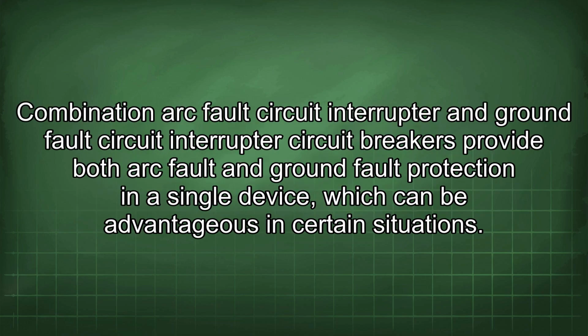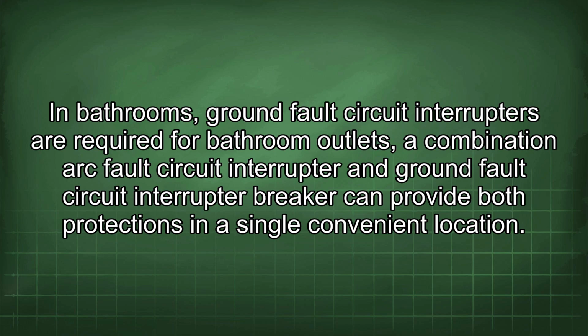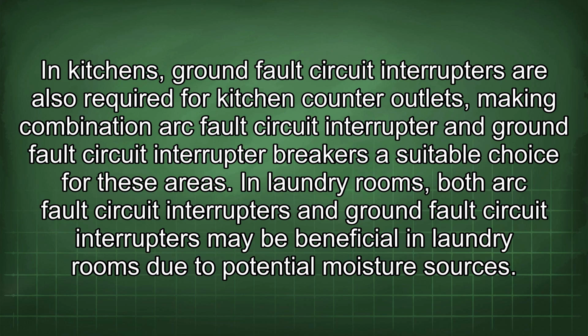Combination arc fault circuit interrupter and ground fault circuit interrupter circuit breakers provide both arc fault and ground fault protection in a single device, which can be advantageous in certain situations. In bathrooms, ground fault circuit interrupters are required for bathroom outlets. A combination arc fault circuit interrupter and ground fault circuit interrupter breaker can provide both protections in a single convenient location. In kitchens, ground fault circuit interrupters are also required for kitchen counter outlets, making combination arc fault circuit interrupter and ground fault circuit interrupter breakers a suitable choice for these areas.